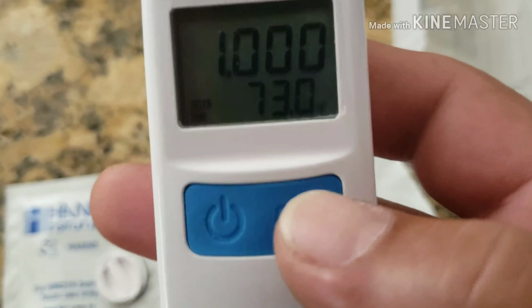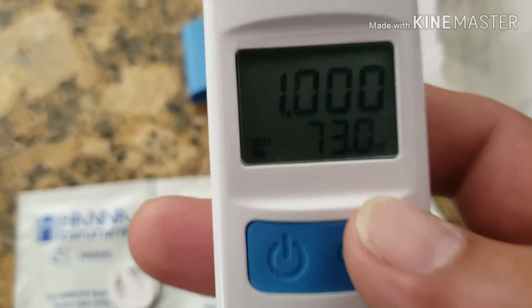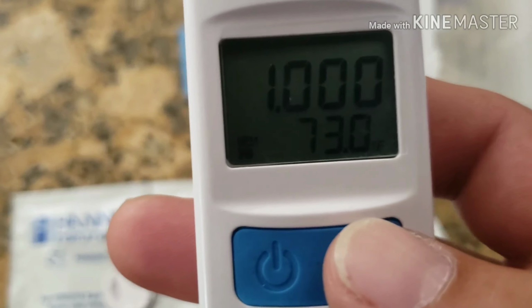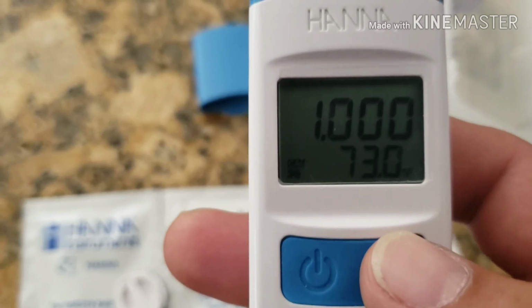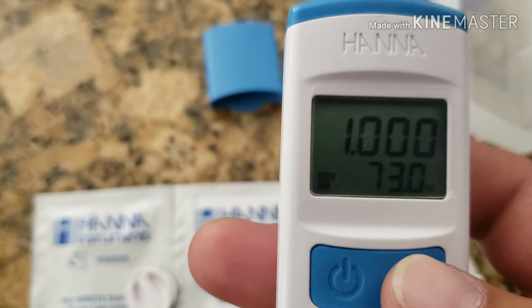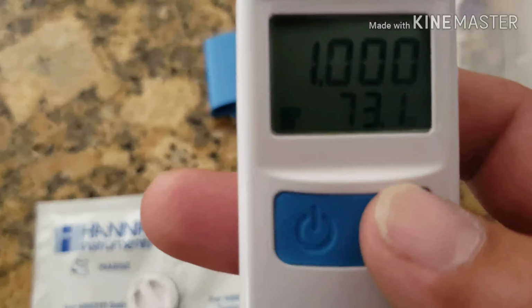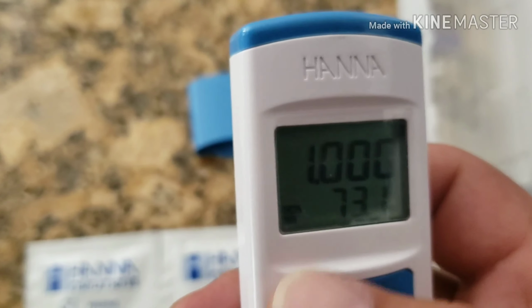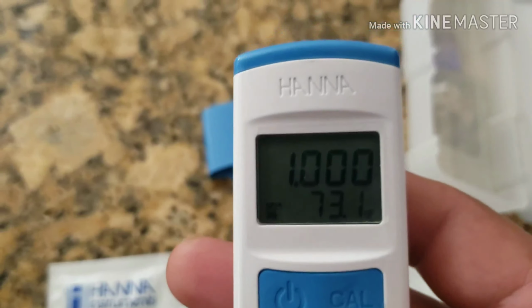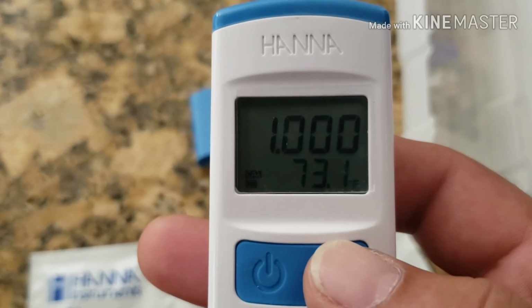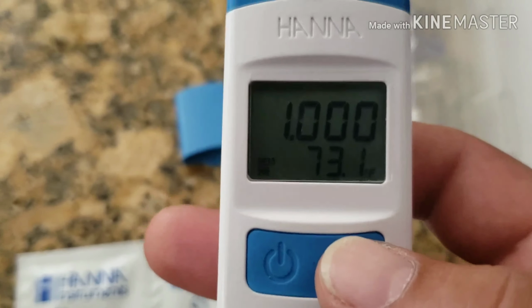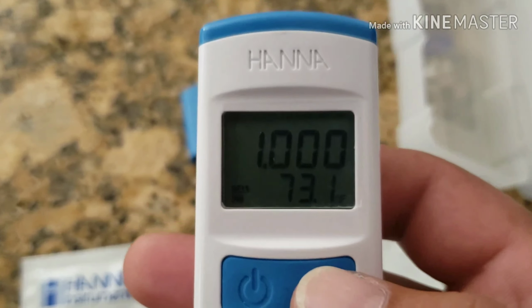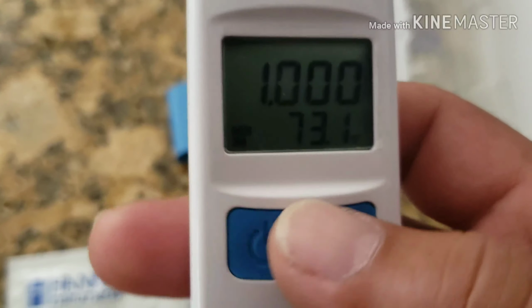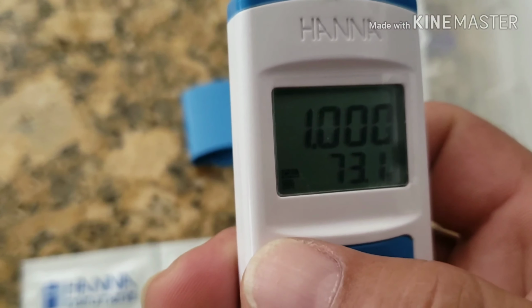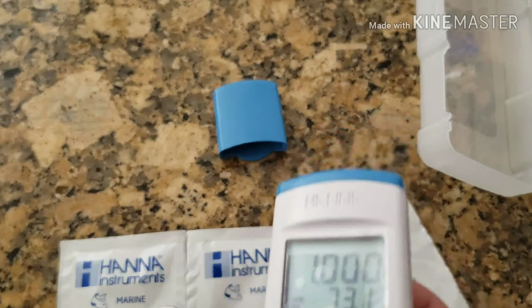and then to change the setting you hit the calibration button. So you hit the calibration button until you see what style you want to read in, whether it be PPT, PSU, specific gravity. So I chose specific gravity. You scroll through using the cal button. Once you hit what you like, then you hit the power button. Then it'll switch over to the temperature mode. You hit the calibration button to switch between Fahrenheit and Celsius. Once you are done selecting which one you want, go ahead and hit the power button again. After that, you're all done.